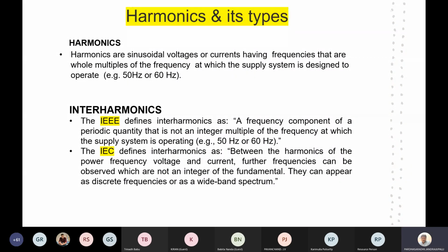What I want to convey at this time is harmonics. Harmonics are sinusoidal voltages or currents having frequencies that are whole multiples of the frequency at which the supply system is designed to operate, maybe 50 Hz or 60 Hz. If the frequencies are multiples of the fundamental frequency, and in Indian standards we are following 50 Hz, suppose the frequency is 100 Hz, then it is a second order frequency. Whereas if it is at 150 Hz, it is a third order component. Suppose it is at 250 Hz, then it is said to be the fifth order harmonic. So we all well know about the harmonics.